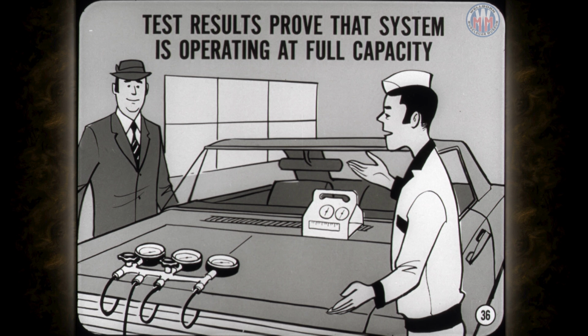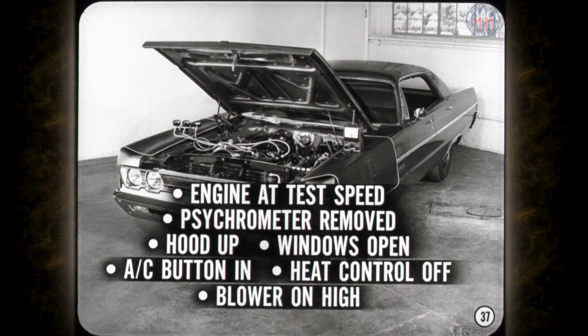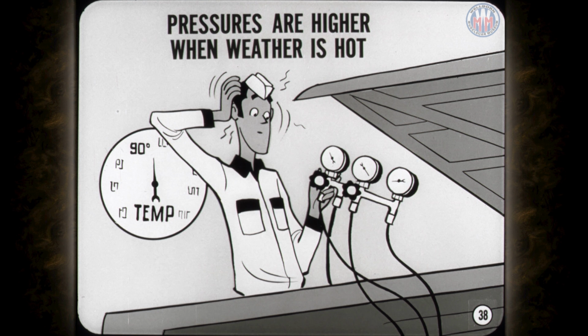Okay, Fred, now what's the story on the preliminary pressure check? Well, we leave the engine running at the same test speed, but we remove the psychrometer and raise the hood. Also, we leave the windows open and the controls set as before. The AC button is in, the heat control is off, and the blower on high. Just remember that overall operating pressures are usually higher than average when the weather is hot. You can easily find the pressures that are typical for average local conditions. Simply note the stabilized pressures after you prove the system is okay with an overall performance test.